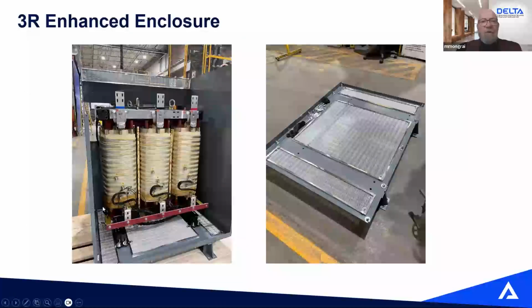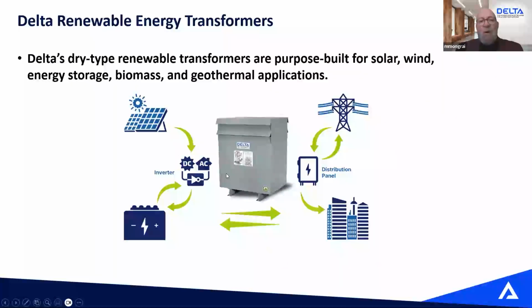When we deal with outdoor, more and more outdoor, as you know, 3R, as per CSA, is approved for outdoor application because it's rated weatherproof. That being said, weatherproof in California or Southern Ontario and weatherproof in up north Manitoba is different.